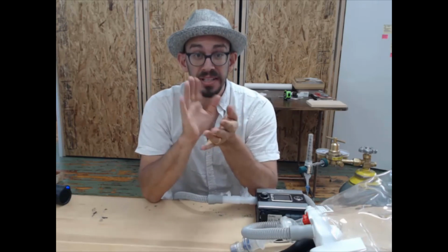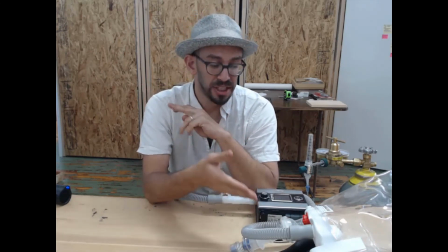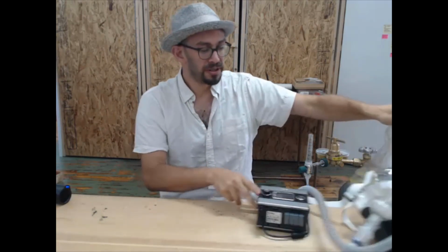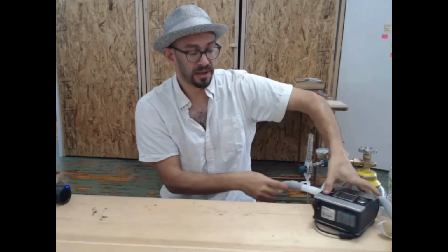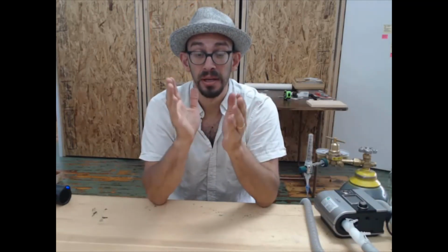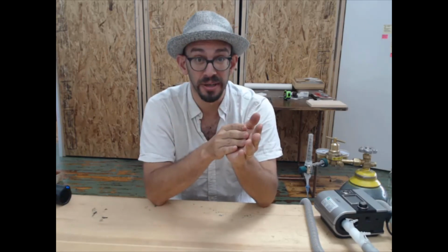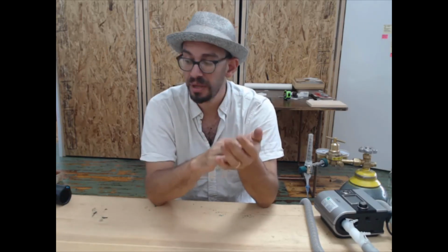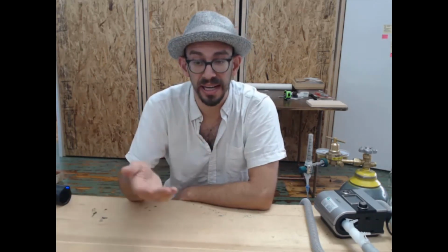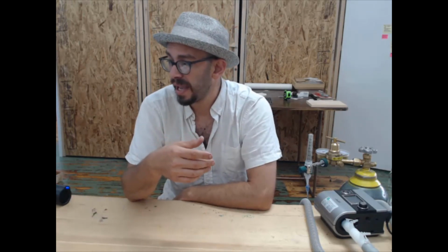That's about it on the details of how to adjust the patient's circuit and the ins and outs of how to work with it. What you'll see, I think, is always this repeated idea that the patient circuit, the way to make it safe, ensure you have adequate flow, at least 50 liters a minute through. There's an operator's manual for every model of CPAP that will show you how to adjust settings for the patient.